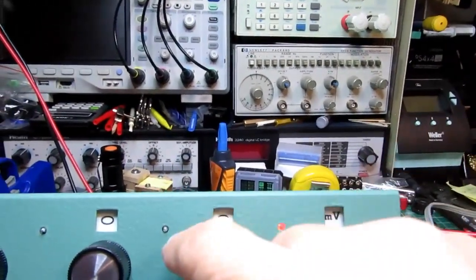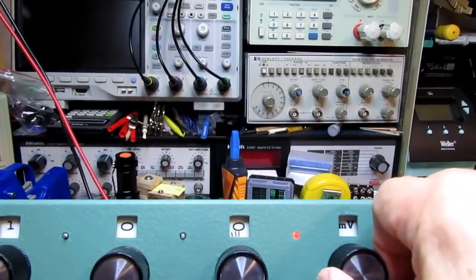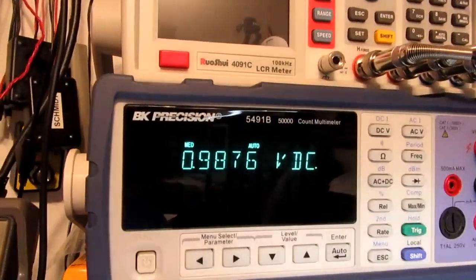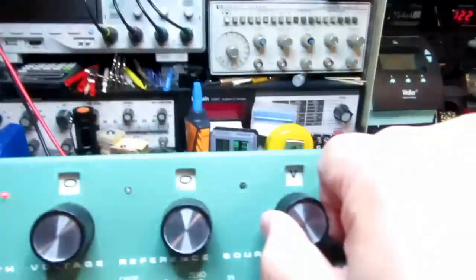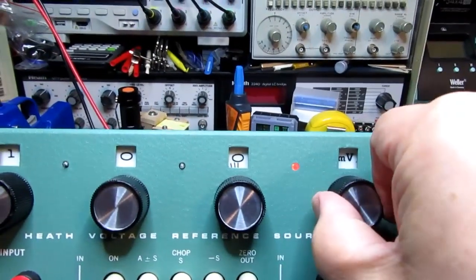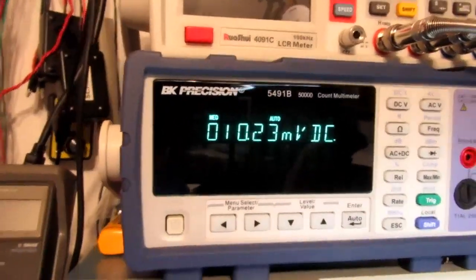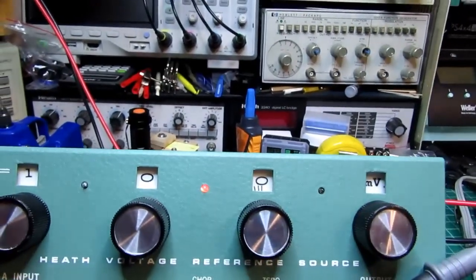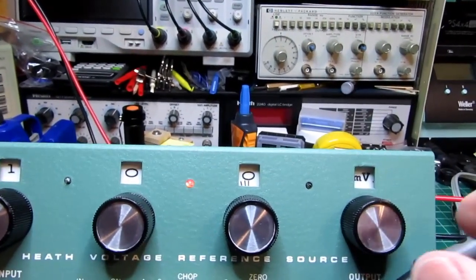Now what if I change the decimal point to here? Then it would read 10 millivolts, right? Well, now 1 millivolt—pretty close. I'll change it so we get that decimal point; it should read 10 millivolts. So that's what that switch does, and the indicators show where the decimal point is. That's your range control.